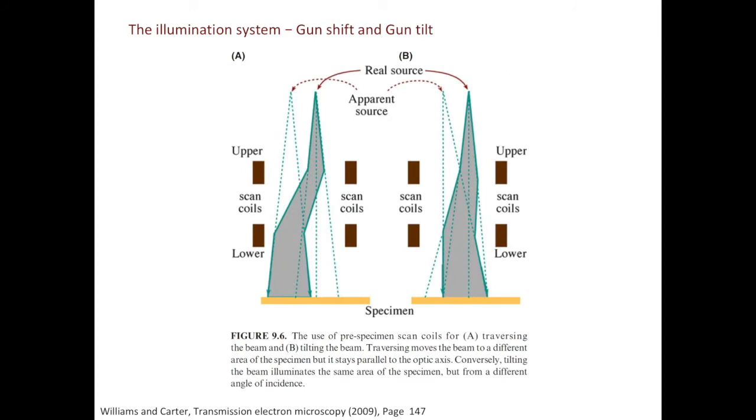The last thing I want to talk about in this video is the Gun Shift and Gun Tilt. If the alignment is not right, the beam can be bent a few times, and the physical location of the source is different from where it appears to be. Such artifact can also lead to the illusion that the beam comes in at an angle instead of coming straight down.